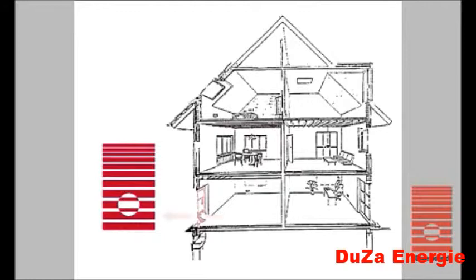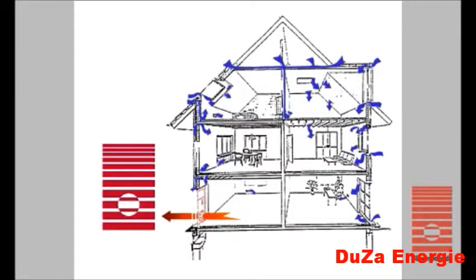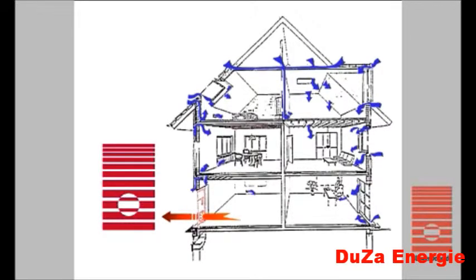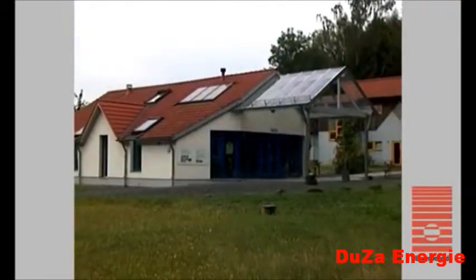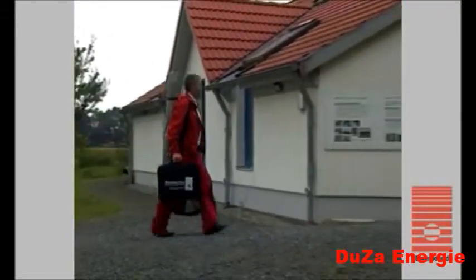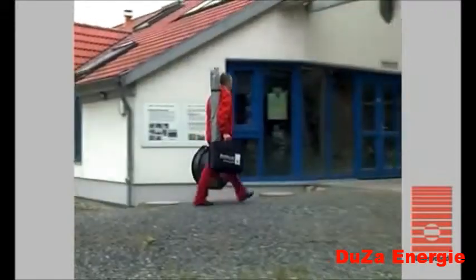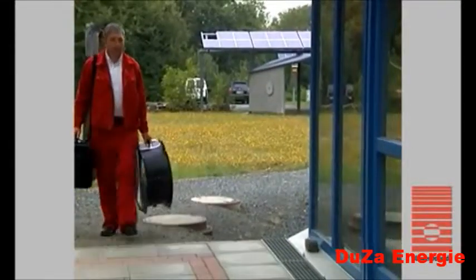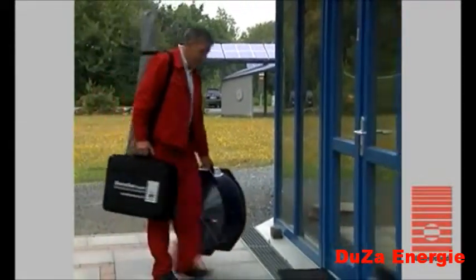The blower door is mounted in an exterior doorway. The fan exhausts air out of the building and generates a depressurization of 50 pascals. During the depressurization test, outside air is continuously drawn into the building through holes and penetrations in the building's envelope, making these leaks easy to locate. The specific building tightness measurement is the air change rate N50.